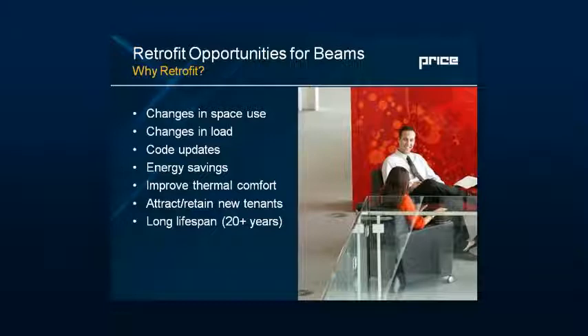If I can improve thermal comfort, I benefit. Thermal comfort can also involve the cleanliness of the air and the amount of background sound — it's all about how the occupant perceives the space. Beams fit in very well here because we're transferring less air, so we have less background sound, less draft, and a higher percentage of outside air for a perception of cleanliness. Beam systems also have a very long lifespan — 20-plus years, and hydronic-based systems installed since the 70s have lasted some 30 years.